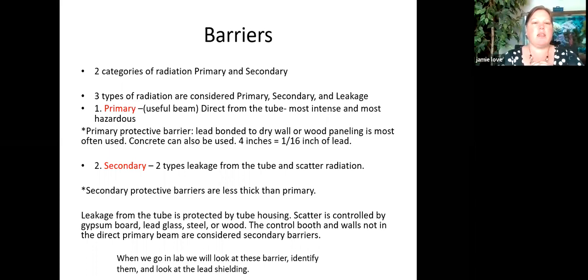To be lead equivalent, we don't have to use lead. We could use drywall, wood, paneling, concrete to equal lead. So they say lead equivalent for primary beam, and you're going to learn all of these amounts, how much thickness it has to be, later on in the program. So we're not teaching you all of that now. We're just telling you what a primary barrier is now. Secondary barrier is to protect from scattered radiation from the tube or the patient. So those are going to be off to the side. They're not as thick as primary because the beam's not coming straight at them.